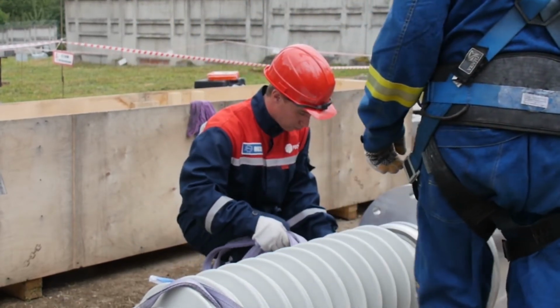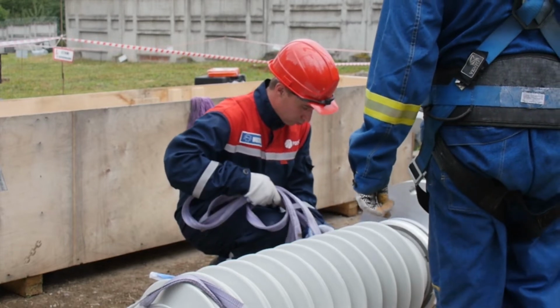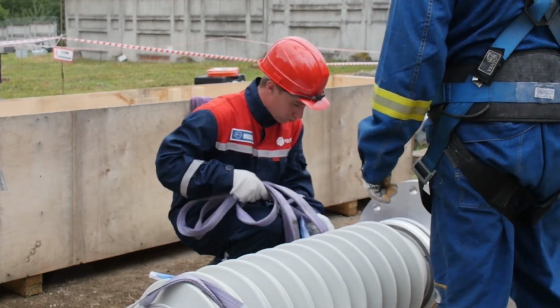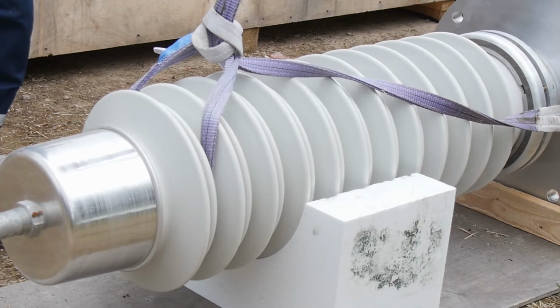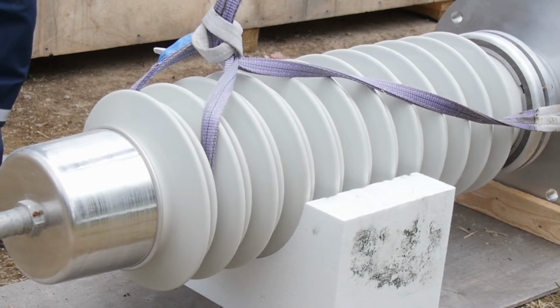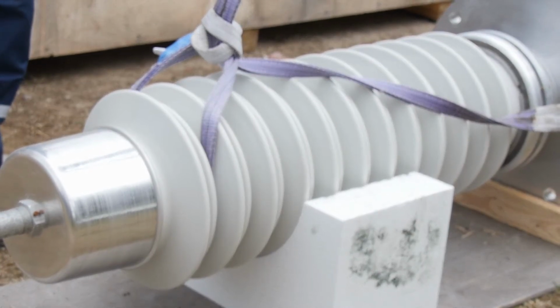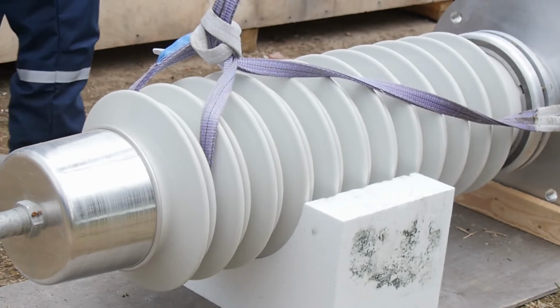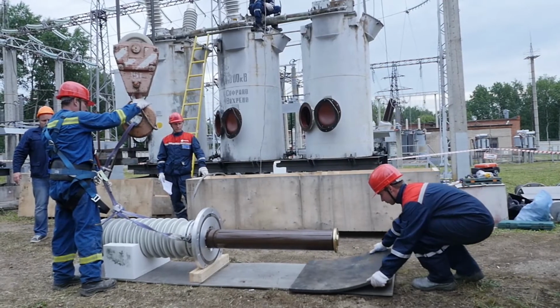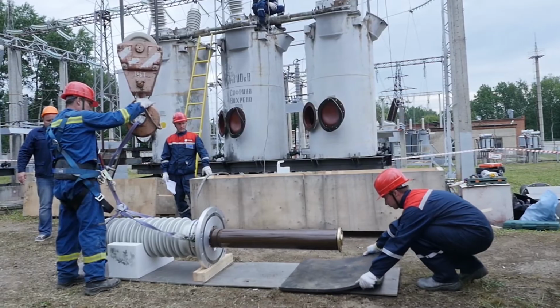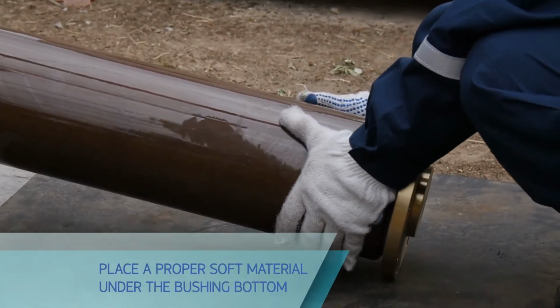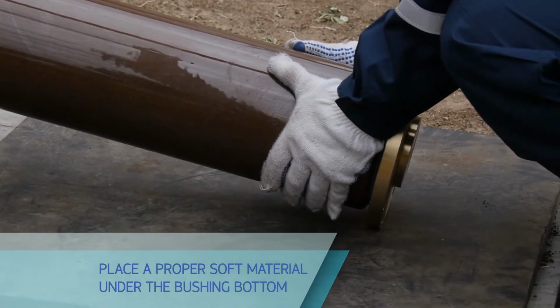Tighten the slings along the housing and secure them, preventing their slipping, having wound an additional sling around each one of them. If necessary, secure these additional slings to avoid slippage. Place a proper soft material under the bushing bottom, rubber or felt. Avoiding the bottom slippage, smoothly set the bushing vertically on a process stand.